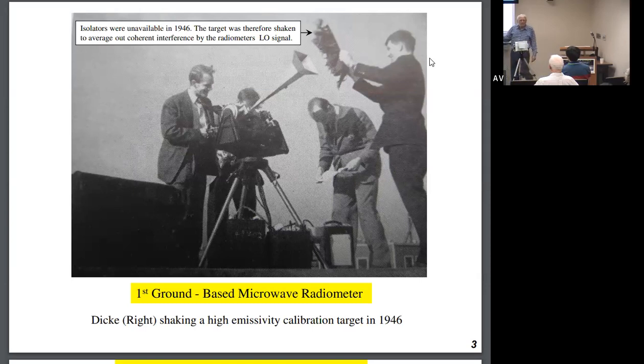Now, what is an isolator? An isolator means that the radiation that this instrument sees only comes from this direction towards the antenna. But there's a problem. If you build a radiometer without an isolator, there's radiation coming in the other direction from the receiver. It's called local oscillator. That local oscillator, if you don't know how to deal with it, it's going to give you trouble. It's going to act like a signal when it gets reflected back into the radiometer from a target. No target is perfect.